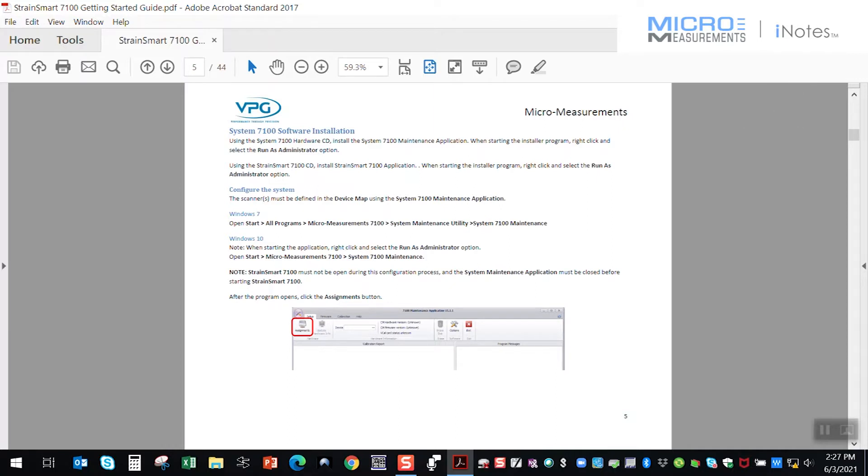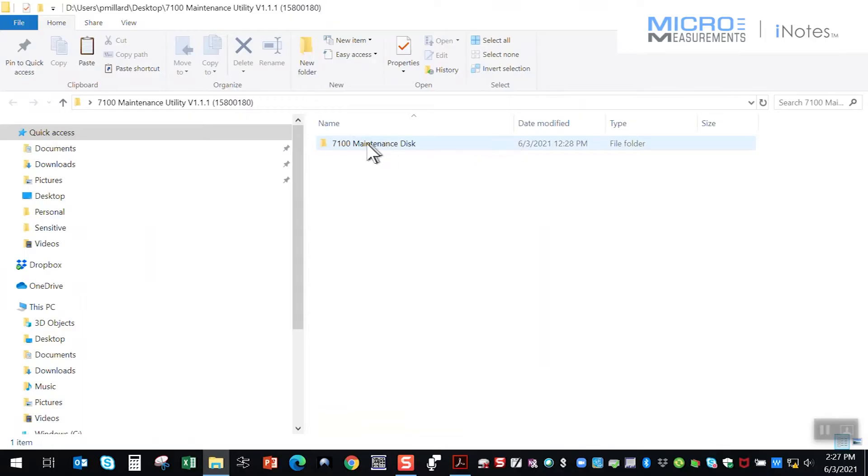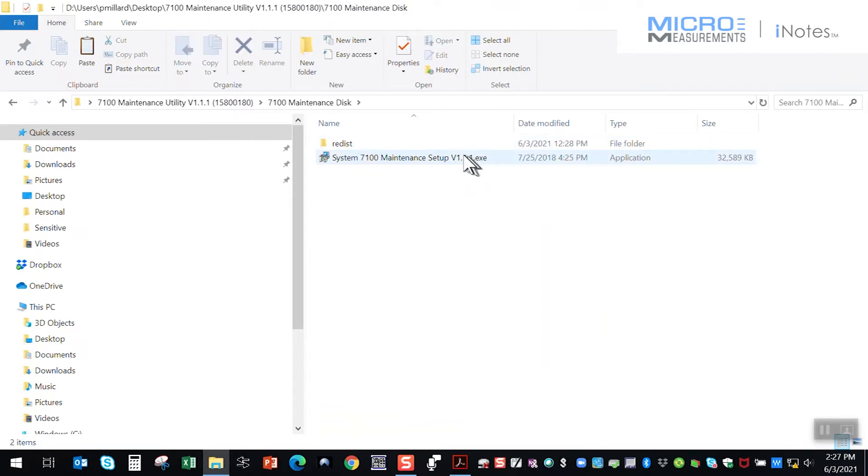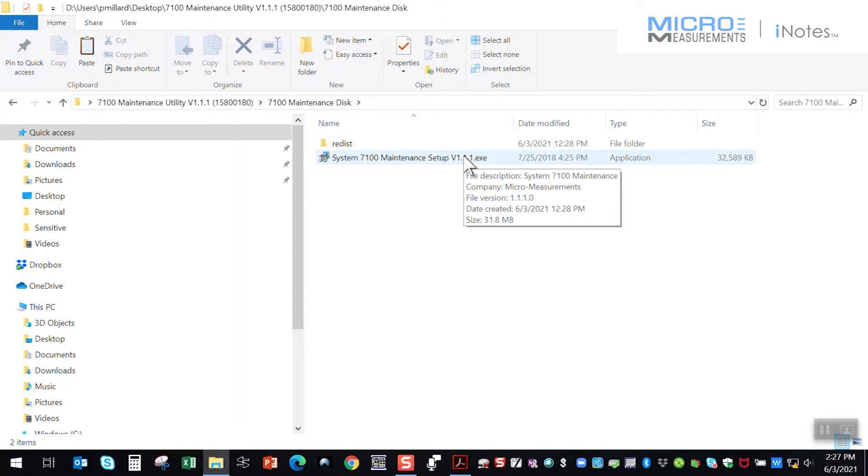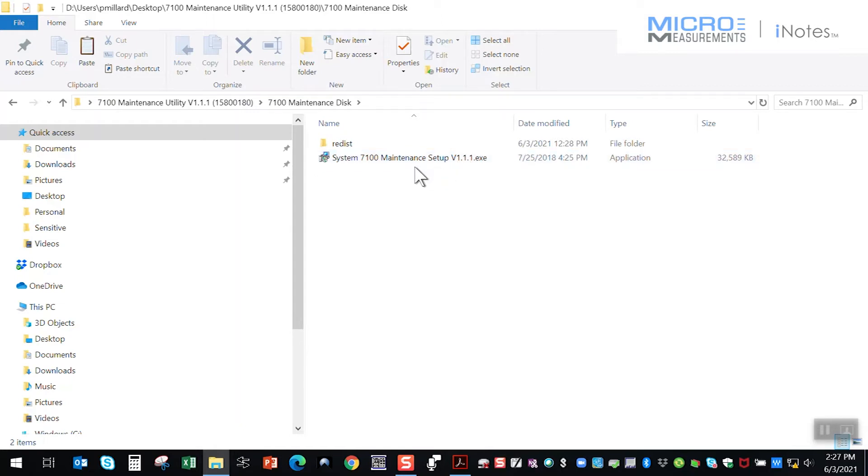So the Getting Started Guide is now referencing using the maintenance utility software, and I've got these three pieces here on my desktop. One's the Getting Started Guide. One of them is the CD that you typically receive with the 7100 system, and that's the maintenance utility. Of course, folks often would push that to a side and jump into the StrainSmart software because they want to get their data. But you really have to run this maintenance utility first. And inside that maintenance utility disk or download, because sometimes we send people updates and upgrades through Dropbox and such, or Jump Drive.